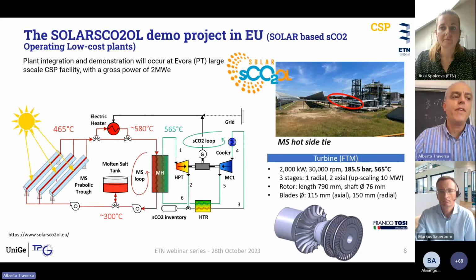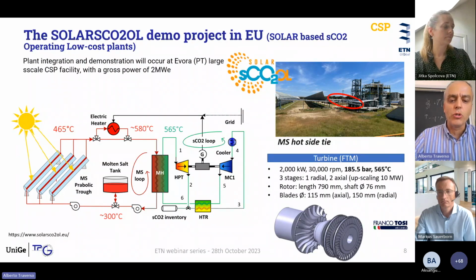And in this case, we can find slightly milder boundary conditions. In particular, we see less than 200 bar inlet pressure, which is 185, and 565 degrees C, which is a little bit exceeding the conventional limit for steam turbines. So in this case, the demonstrator will be carried out in Europe at a lower size and will represent an important benchmark for the industry.